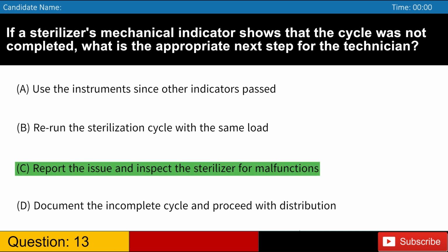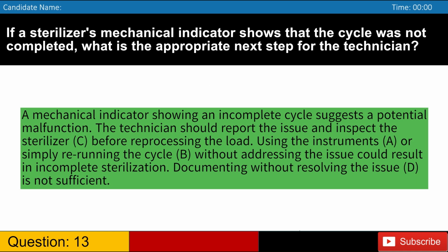Answer: C. A mechanical indicator showing an incomplete cycle suggests a potential malfunction. The technician should report the issue and inspect the sterilizer, C, before reprocessing the load. Using the instruments, A, or simply rerunning the cycle, B, without addressing the issue could result in incomplete sterilization. Documenting without resolving the issue, D, is not sufficient.